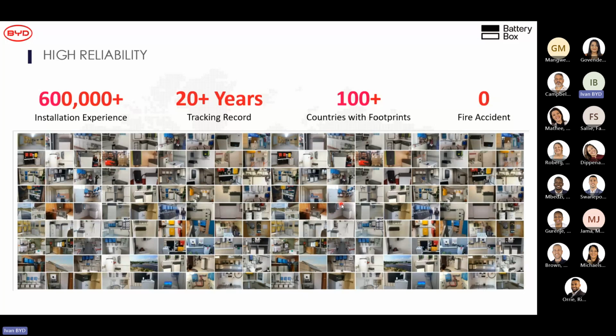The cells ruptured, the electrolyte flowed out, and there were various internal shorts, because the cells ruptured and expanded and shorted on the chassis, and it was in the server room. And the people were working in the server room. So this happened on a weekend, and in the morning, people came back into that server room and worked in the server room. There was no flame, there was no fire.